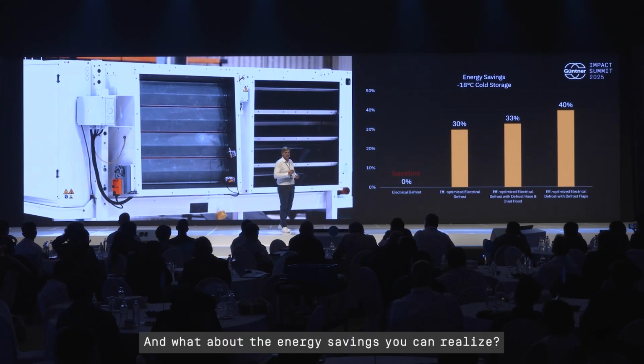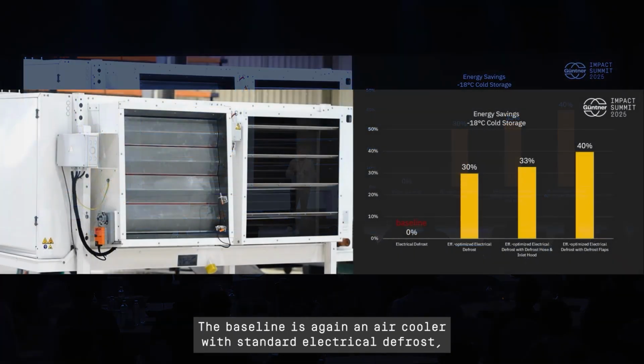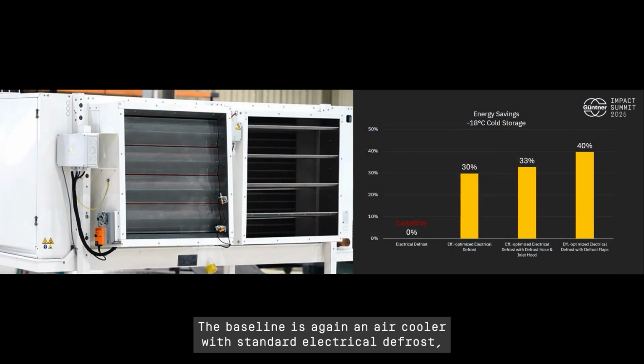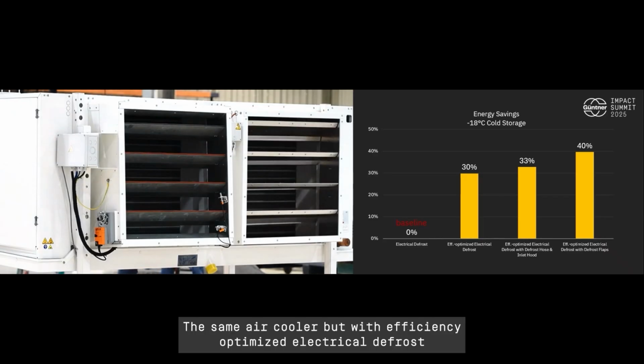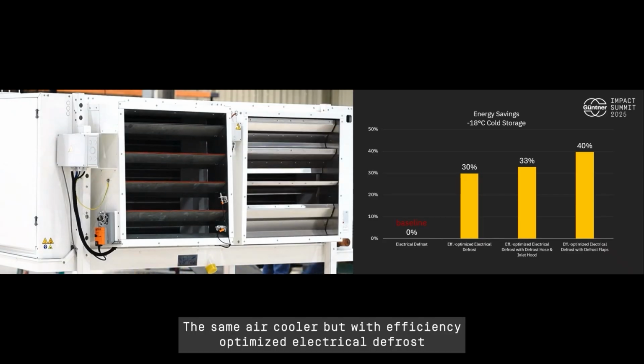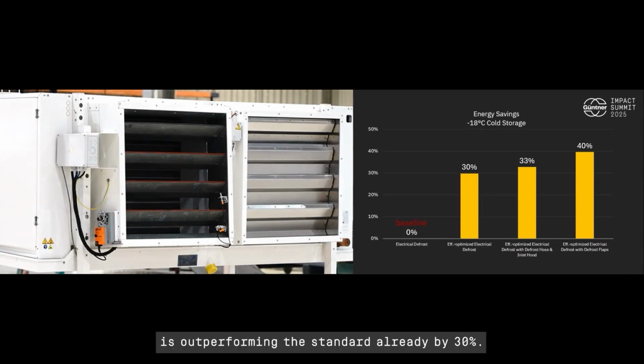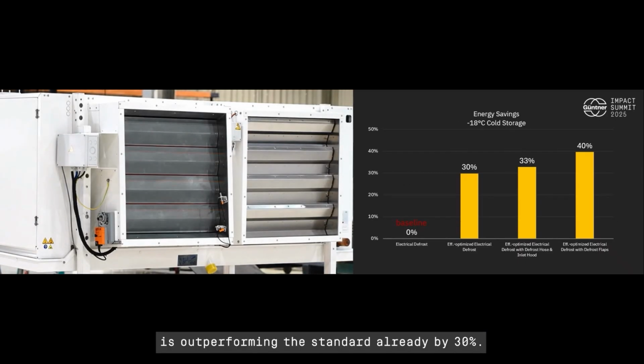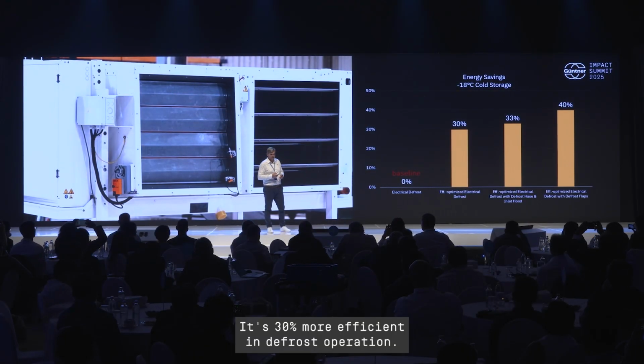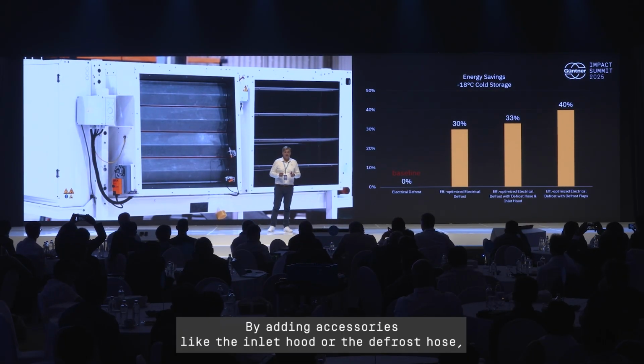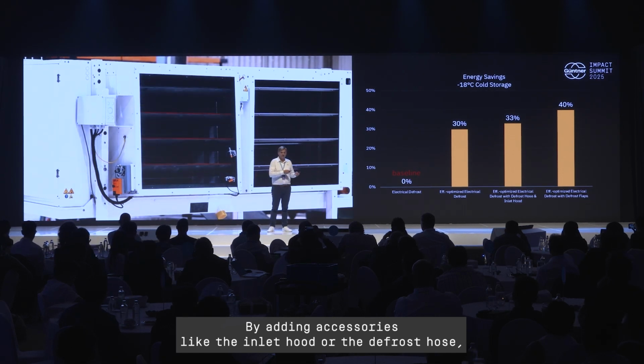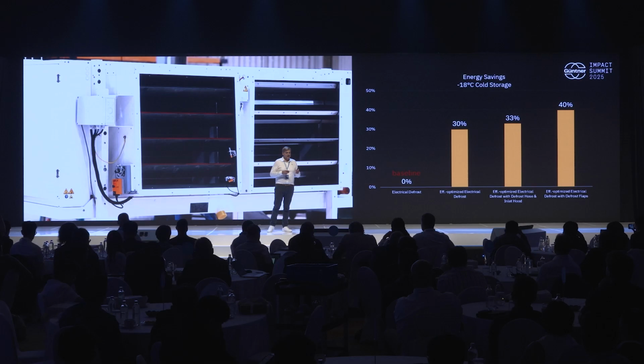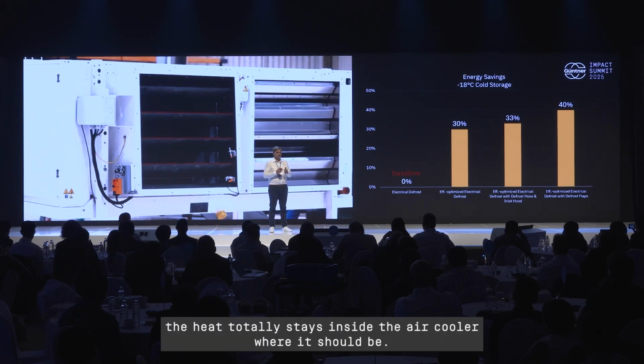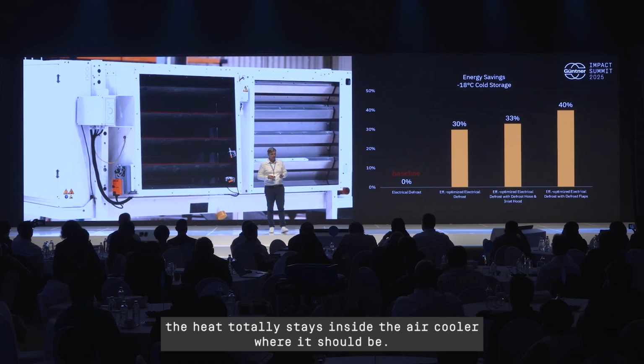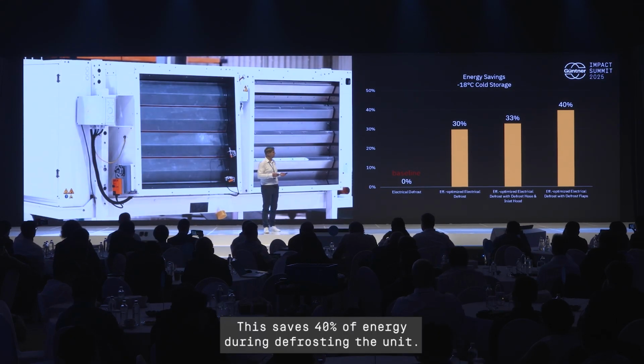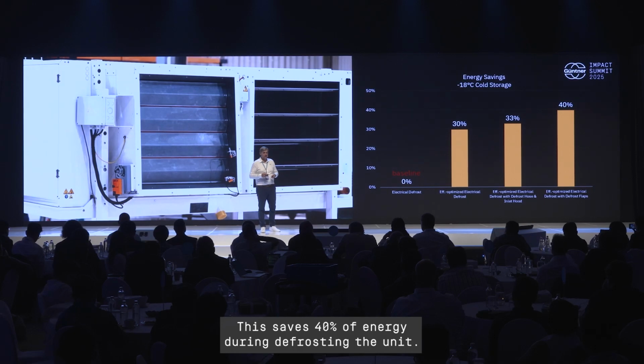And what about the energy savings you can realize? The baseline is again an air cooler with standard electrical defrost, no accessories attached. The same air cooler with efficiency-optimized electrical defrost already outperforms the standard by 30%—that's 30% more efficient in defrost operation. By adding accessories like the inlet hood or the defrost hose, it gets even better. And with the defrost flaps, the heat stays totally inside the air cooler where it should be, saving 40% of energy during defrosting.